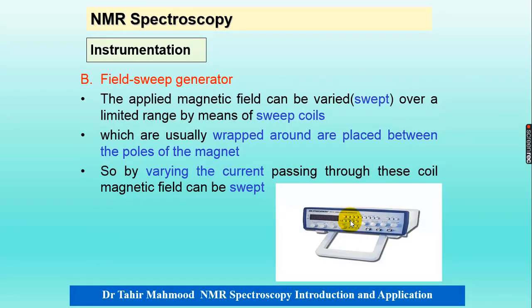The second component is the field sweep generator. Because we have two modes — we can vary field strength or frequency — the applied magnetic field can be varied over a limited range by means of coils usually wrapped around the poles of the magnet. By varying the current passing through these coils, the magnetic field can be swept.